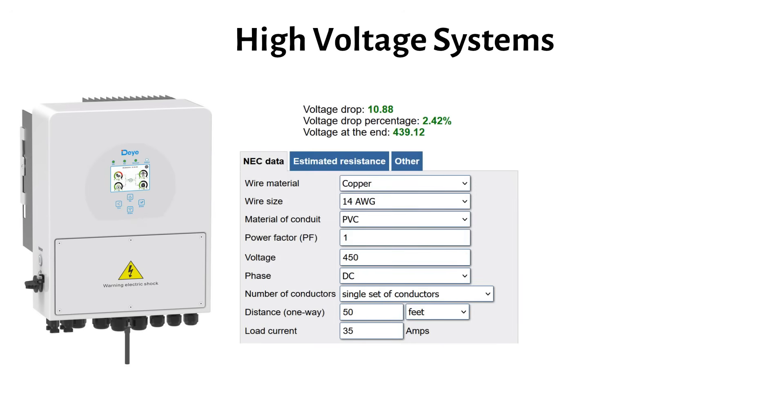For example, if we change the voltage to 450 volts and the current to 35 amps, the calculator might say that 14 gauge or 2.5 mm square has a voltage drop of 2.42%. That's good, right? Not so quick.